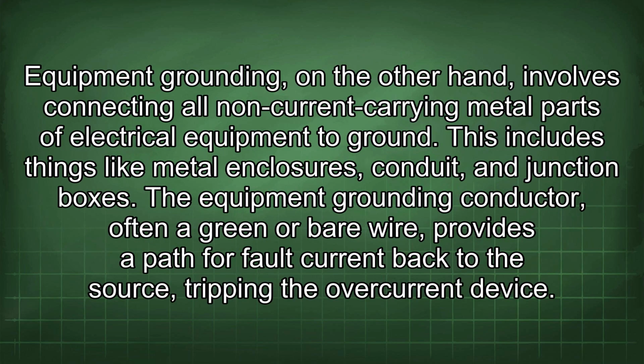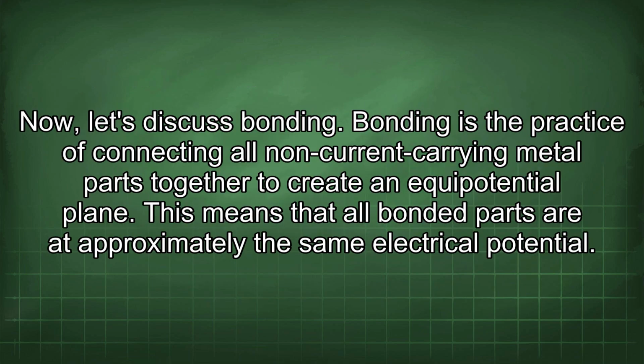Equipment grounding, on the other hand, involves connecting all non-current carrying metal parts of electrical equipment to ground. This includes things like metal enclosures, conduit, and junction boxes. The equipment grounding conductor, often a green or bare wire, provides a path for fault current back to the source, tripping the overcurrent device. Now let's discuss bonding.